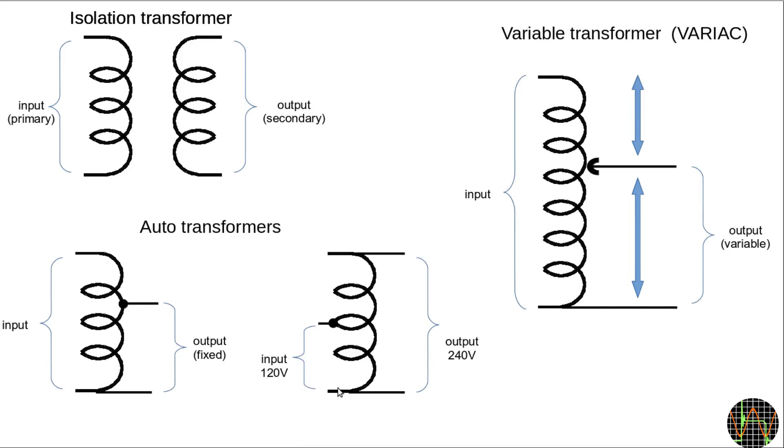The important thing to remember is that the autotransformer is not isolating. So even if the output is say just 12V, it is not safe to touch because you are still electrically connected to mains.